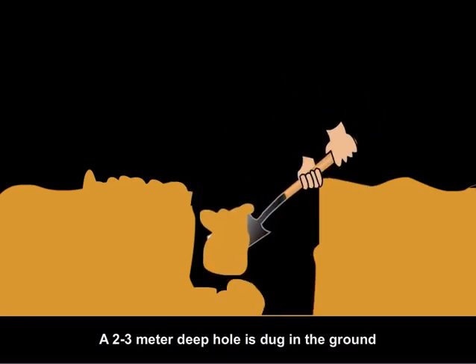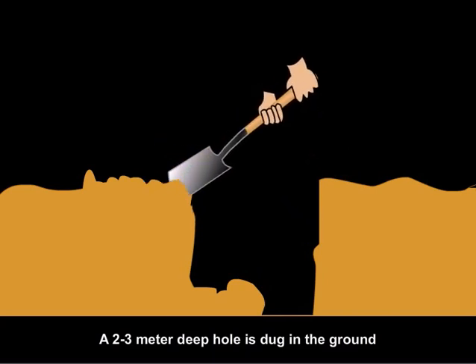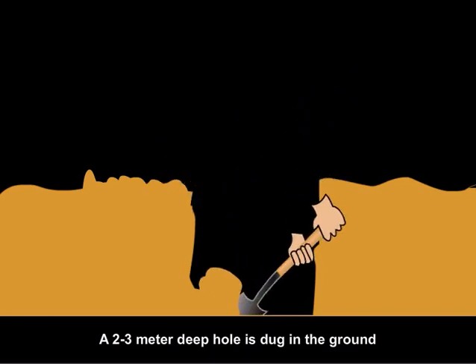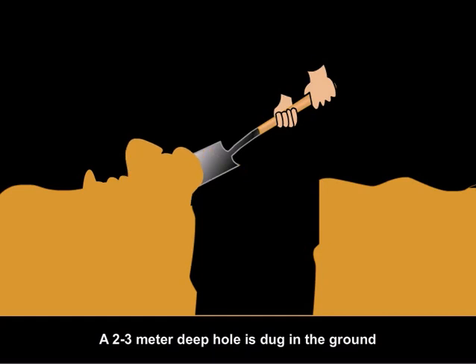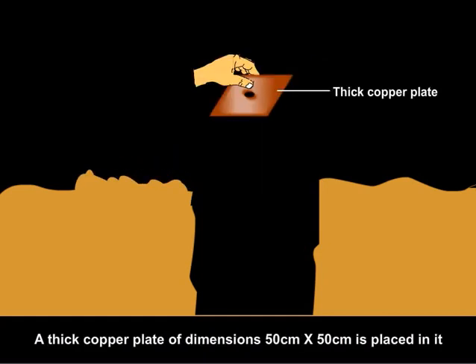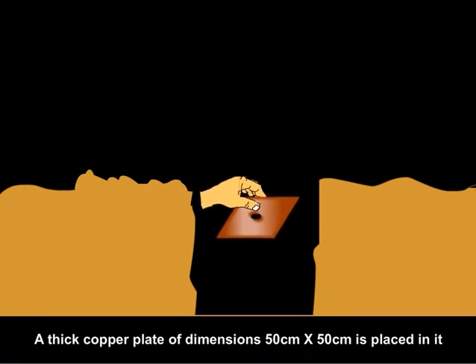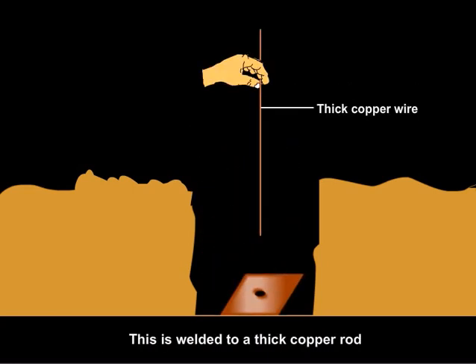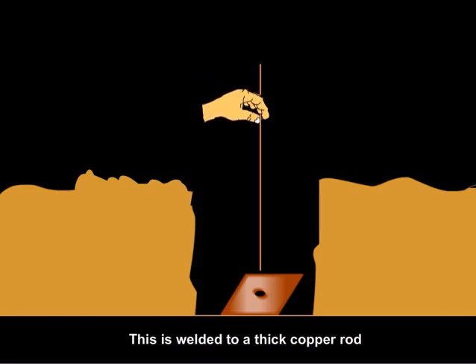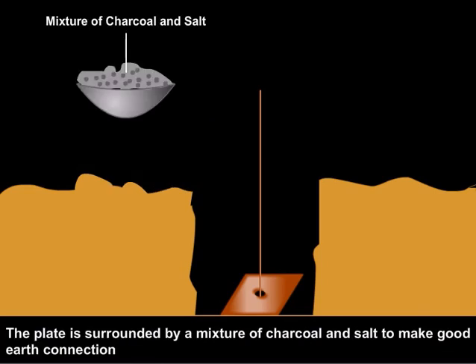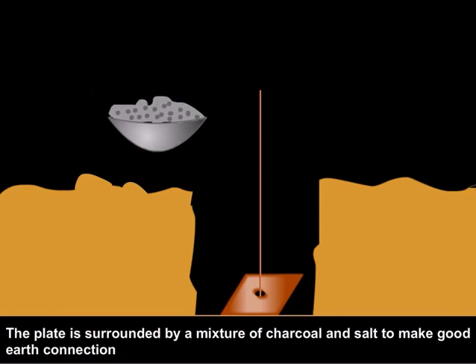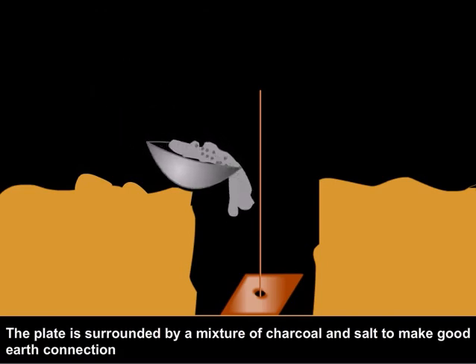To make earthing, a 2 to 3 meter hole is dug in the ground near the house. A thick copper plate, roughly half meter by half meter, is placed in the hole and welded to a thick copper rod. The plate is covered with a mixture of charcoal and salt to make good connection with earth.